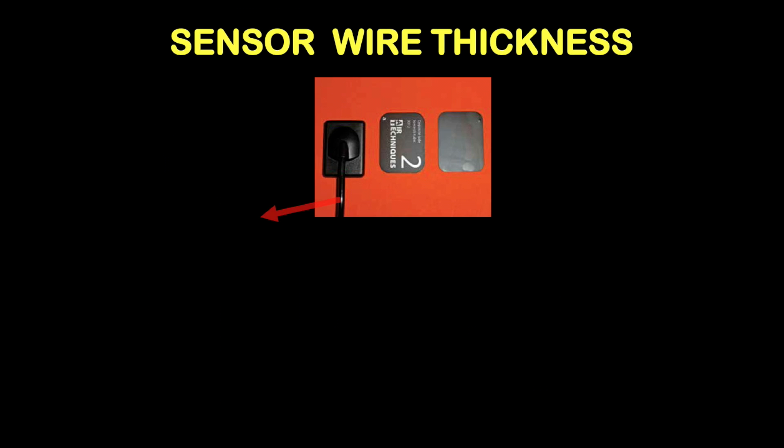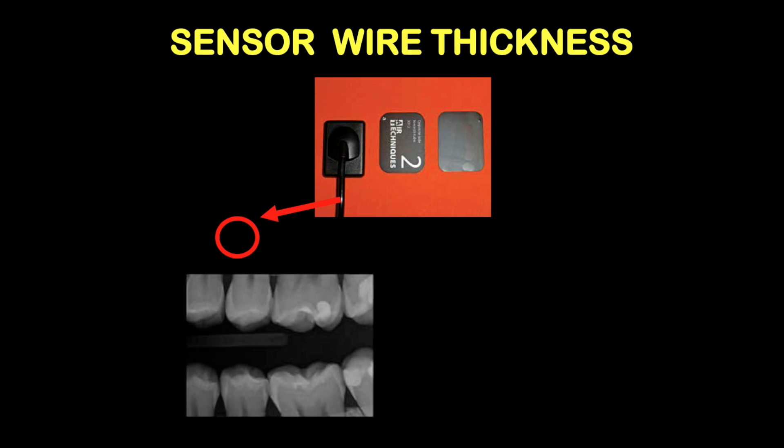The next issue is that of sensor wire thickness. This is something that very often is not immediately observable. But any wired sensor has a thickness of wire that must go in between the teeth. This separates the teeth and leaves an area of darkness, totally non-diagnostic, that doesn't show any oral tissues. And this is the wire that has to go in between the teeth to allow the sensor to be placed on the lingual.